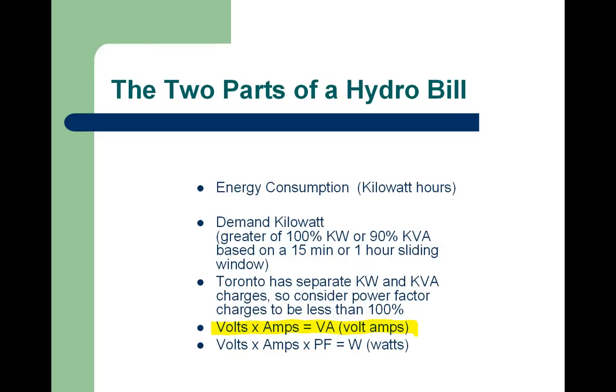Toronto Hydro, as I mentioned, has a slightly different billing method, and since 2001, I believe, or 2000, they now bill on a kilowatt and a separate kVA charge. So whereas in Mississauga, for instance, with 100% kilowatt and 90% kVA, if your power factor is at 95%, there is no recovery of any demand charges. However, in Toronto, because it's a separate kilowatt and kVA, there is a power penalty recovery basically right up to 100%.